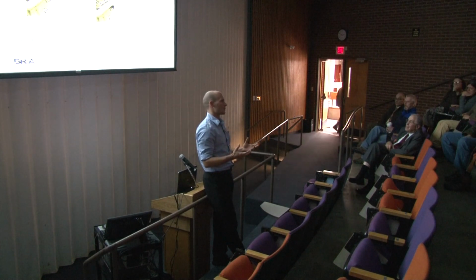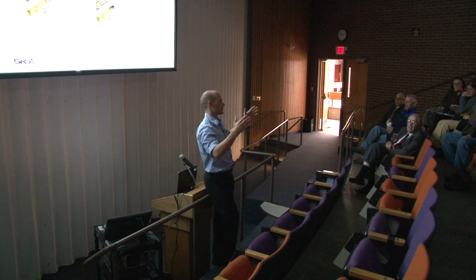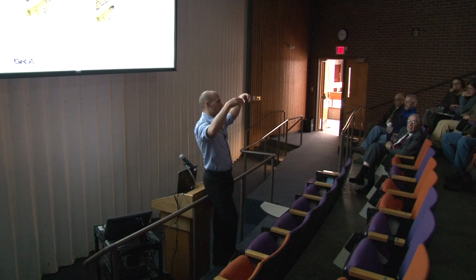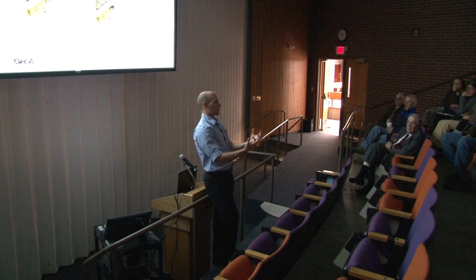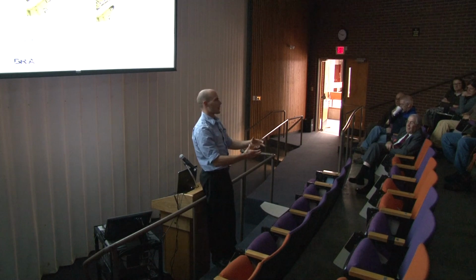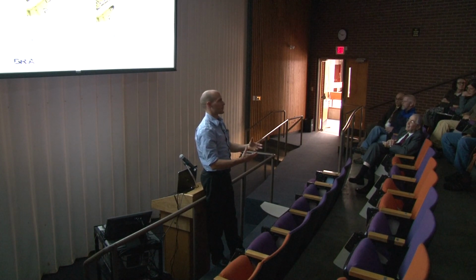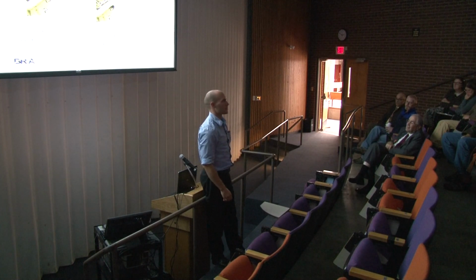The great thing about these is they're actually used in critical building systems like smoke evacuation in buildings with very large atriums, where you need to have smoke evac fans on the roof in case there's a fire because the upper levels can get flooded with smoke otherwise. The smoke evac fans will turn on, and to get air into the building to make up for that exhaust, the windows will open. We may not actually use a UL rated unit, but we'll use one that has that same robust quality, something as reliable as what life safety would depend on for operation. So these little units are really well engineered to make sure they'll continue to operate for the long haul.